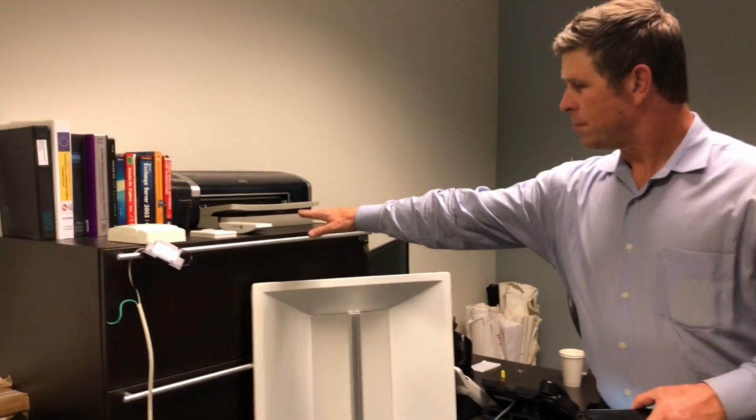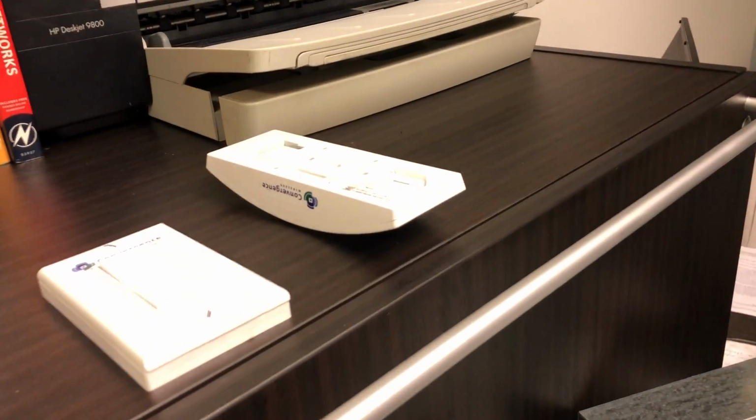So we're going to wait for the algorithm to pick up the fact there's no light coming in. I've turned the light level sensor upside down so it's not going to pick up any light in the space. And now you have the light coming back on because it's saying, hey, there's no daylight, we're going to have to use all the artificial light.